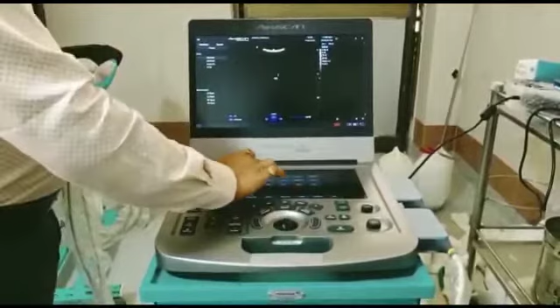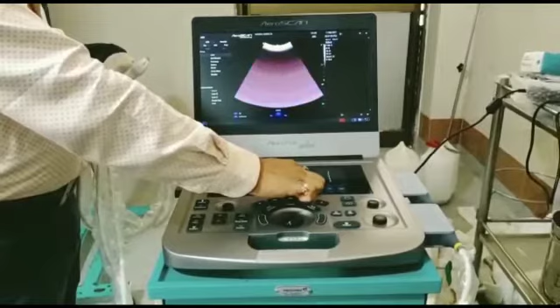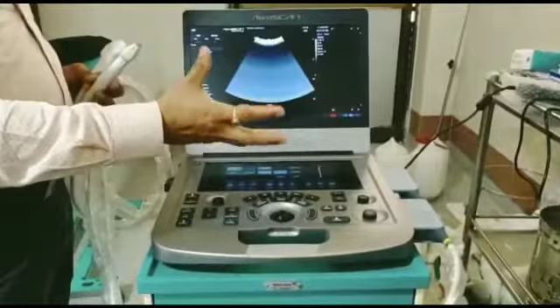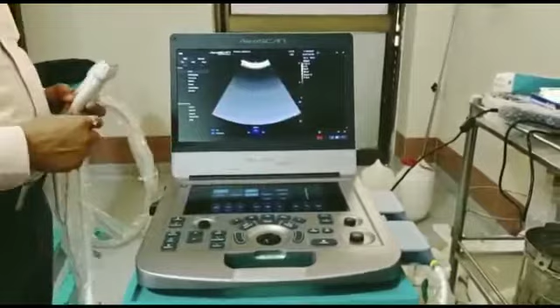This is the gain button. This is the overall gain button to increase the overall gain of the screen. And this is the TGC button. You can change the TGC from here. You can change the frequency, you can change the focus number, focus position, dynamic range, power, and the color tint. Like this is the color tint, these are the color tint you can get to differentiate between organ wall. And after changing this, there is a one button to go back to the by default grey map.